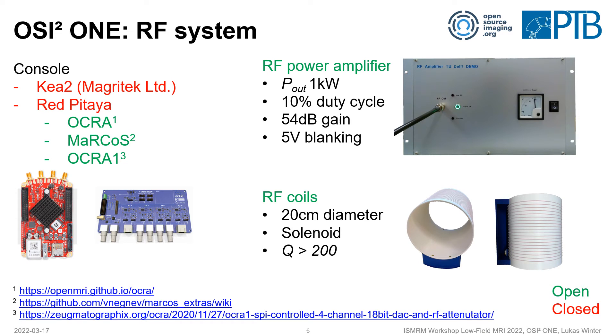After the magnet, let's look at the RF system, where we have a console which at this stage is not completely open source hardware. Currently the Kea 2 is being used for pulse generation, but there is a cheaper option using a Red Pitaya, which is a software defined radio. Together with an Ocra 1 board to drive the gradients and software such as Ocra or MaRCoS — also presented at this workshop — this can be used as a console. We also have an RF power amplifier, an open source hardware design by TU Delft, with one kilowatt peak power and a 10% duty cycle.